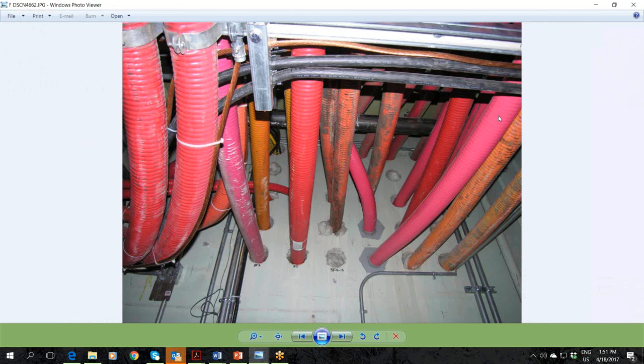Some of that in the last few years, and certainly we're anywhere between about 30% to 70%. There's about 6 of our 100 buildings above 80%, but the vast majority are hovering right around 10 or less. That's even taking into account the requirement for the alternate supply through the transformer. Of course, you can't load that past 50%, right? But even with that taken into account, they're still quite lightly loaded in general.